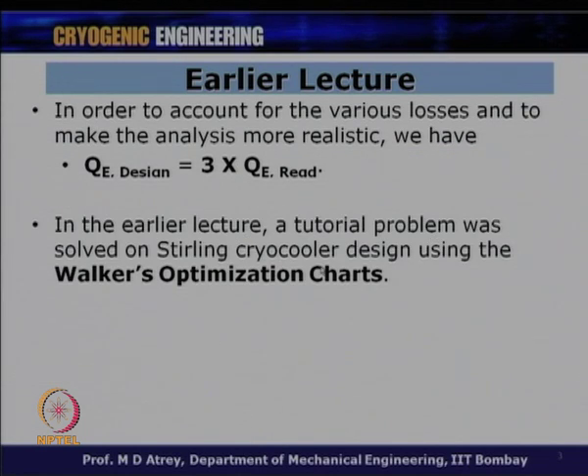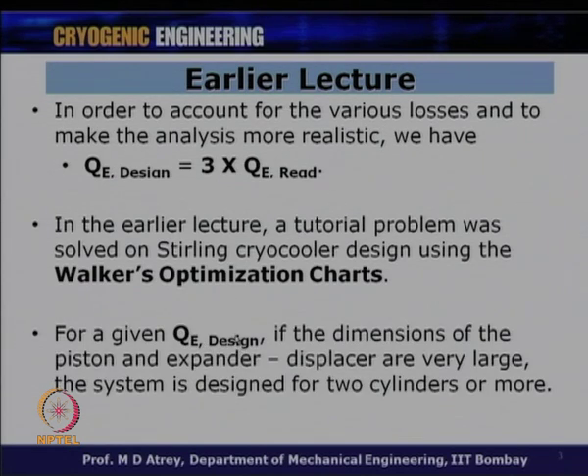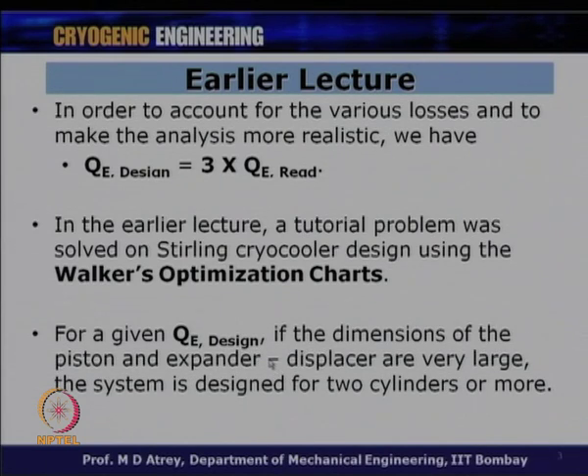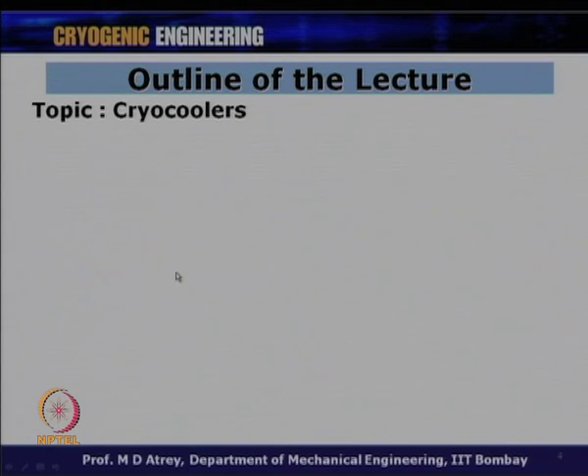In the earlier lecture, a tutorial problem was solved on Stirling cryocooler design using Walker's optimization chart. When we say design, we basically intend to calculate the diameter and stroke of the piston, and the diameter and stroke of the displacer. For a given QE design, if the dimensions come out very large, the system is designed for two cylinders or more — similar to how a four-cylinder automobile generates more power than a single-cylinder one.